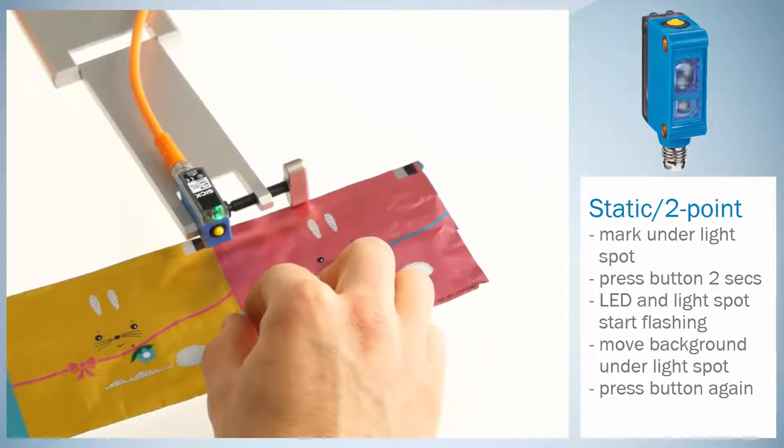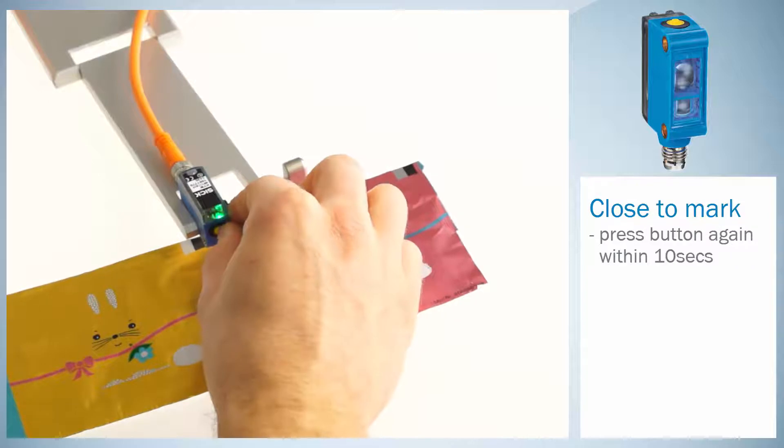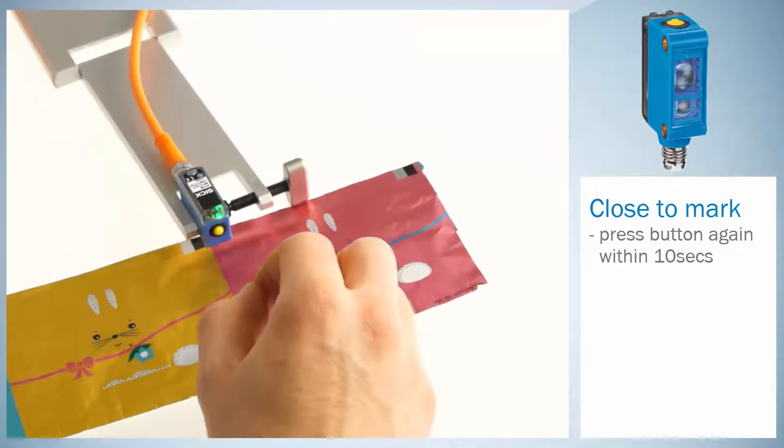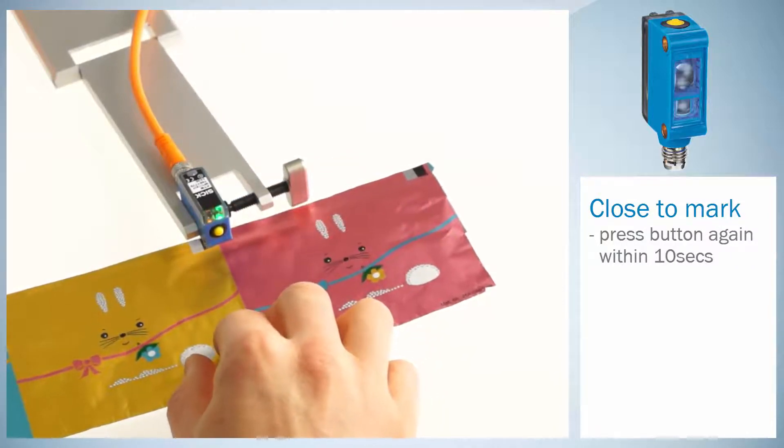If the yellow LED switches off, the teach-in process was successful. If the teach-in button is pressed again within 10 seconds after the teach-in process, a so-called close-to-mark teach is performed.